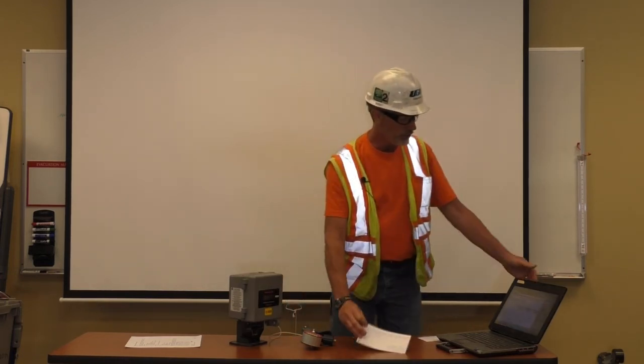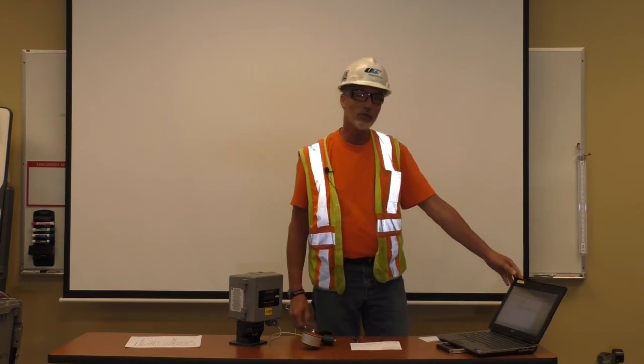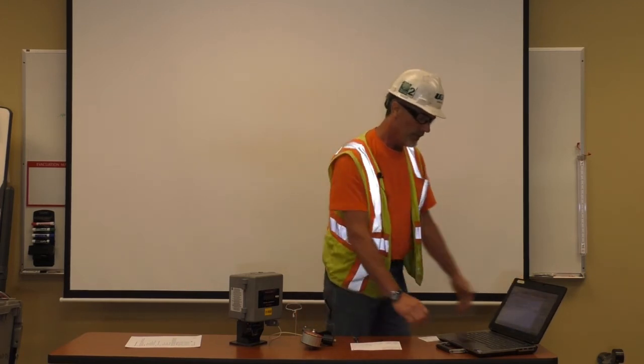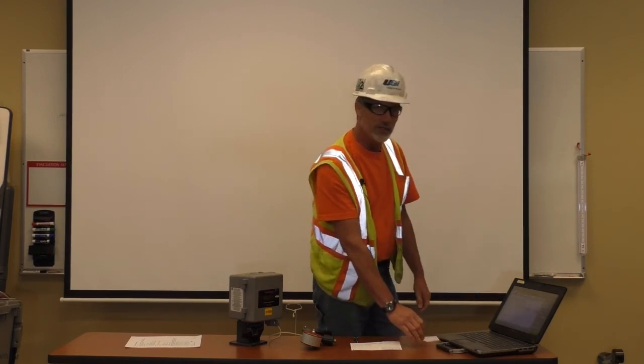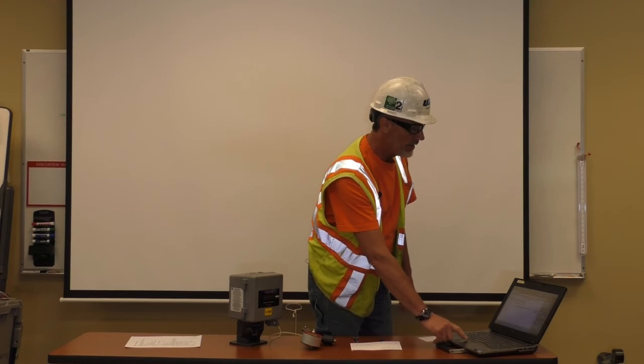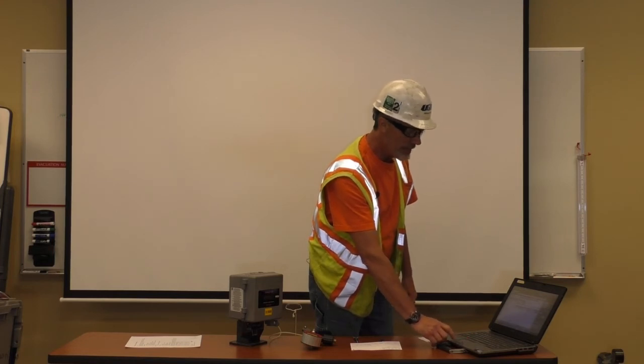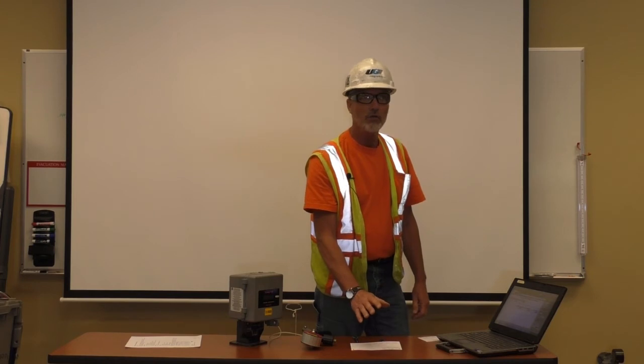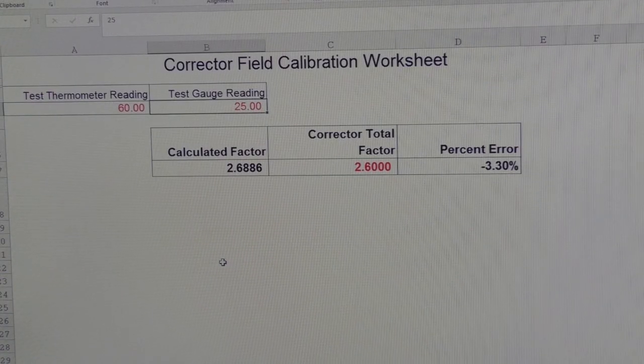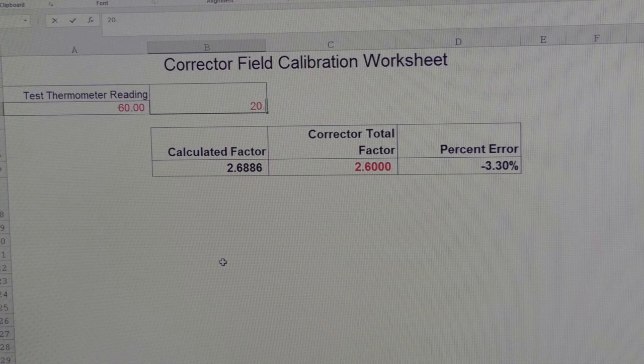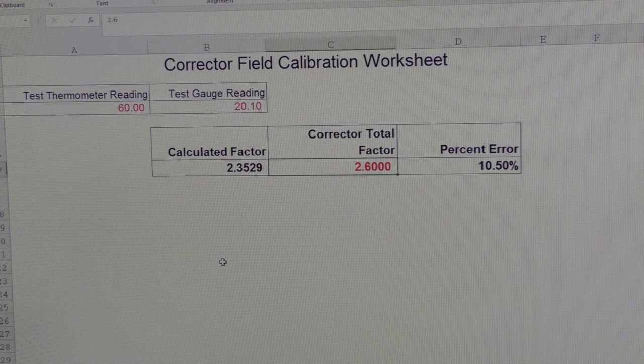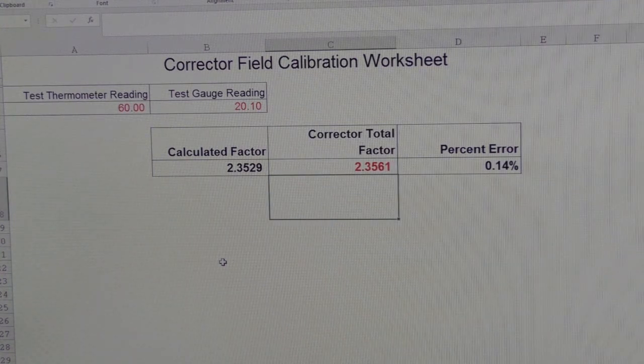The next step you will do is go to your corrector field calibration worksheet on your MDT. The test thermometer reading will be 60 degrees. The next field that you will enter your information at is the test gauge reading on our low side, which is the 20-pound read, we were at 20.1. Enter that into that field. Hit enter, and it will give you your percent error.